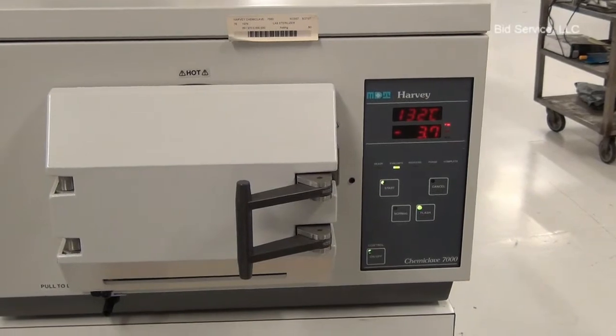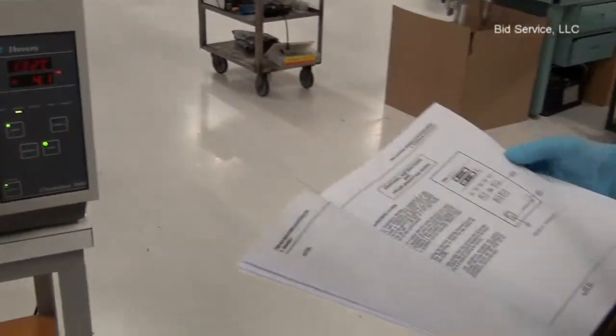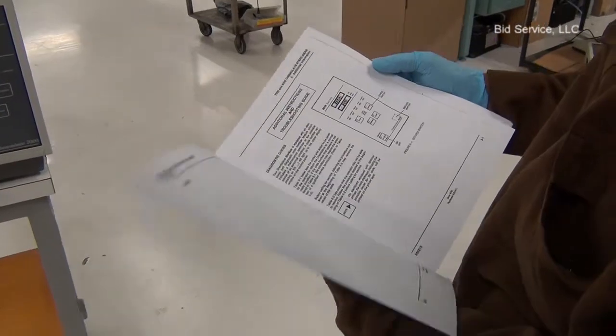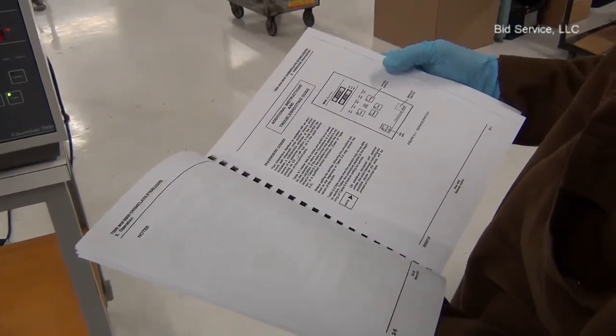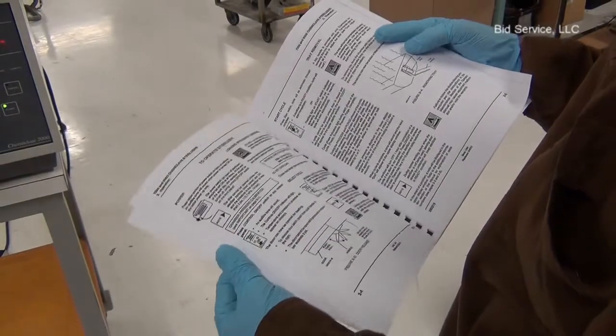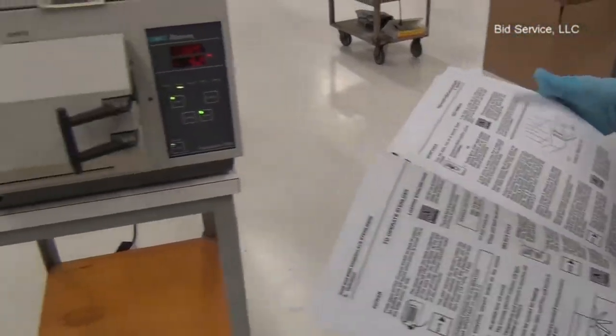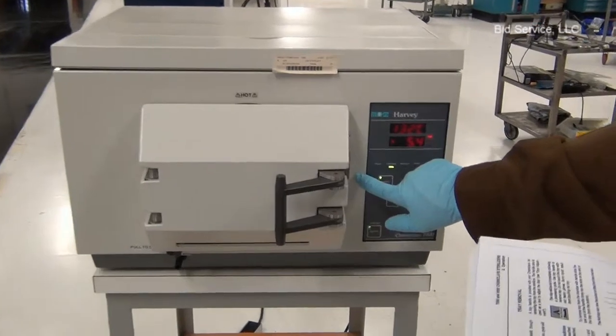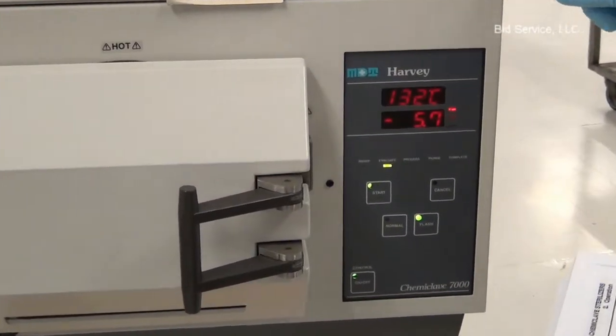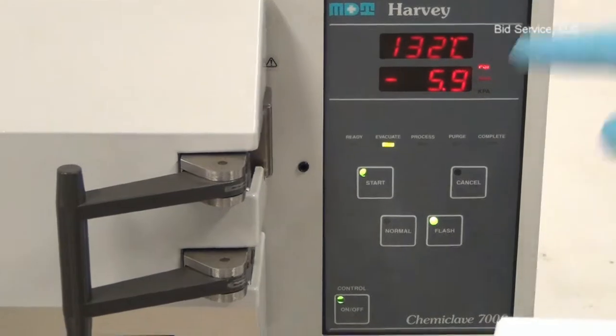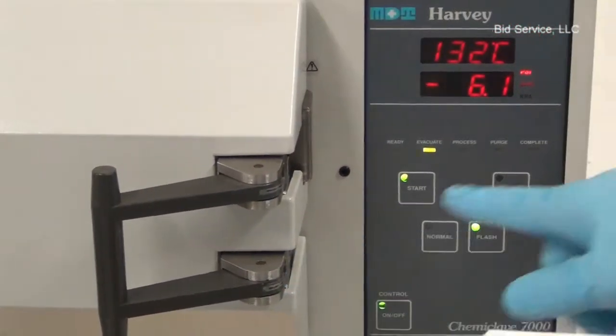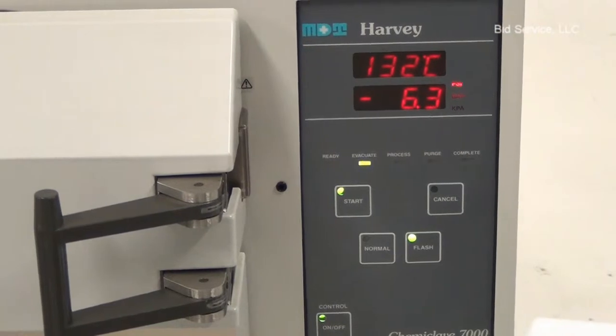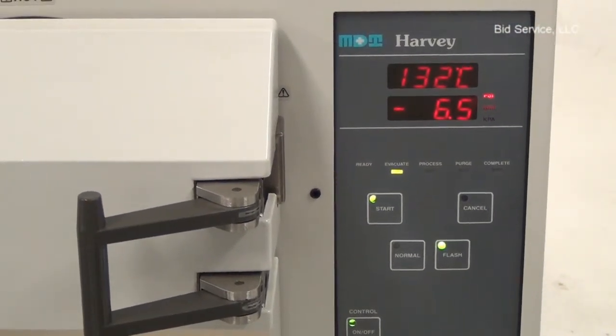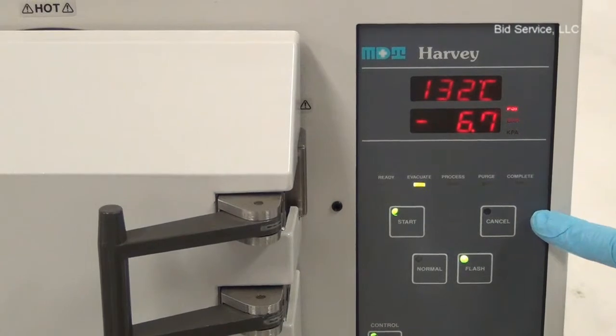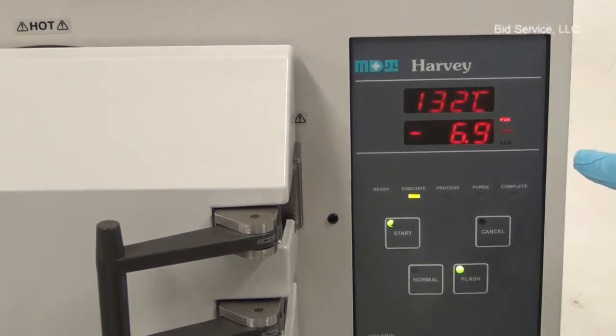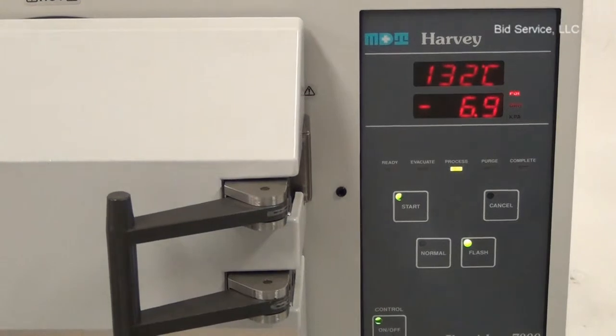The system will be included with the user's manual, the operator's manual, which also includes service manual. There's a door latch release hole here. If at any point of time the door needs to be opened during the process cycle, the door won't be opening unless the pressure inside the chamber is below 2 psi. So in order to release it, first we have to press the cancel button to end the cycle and wait till you hear the door unlatching.